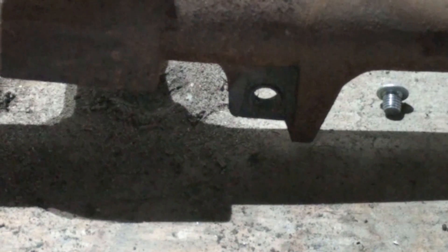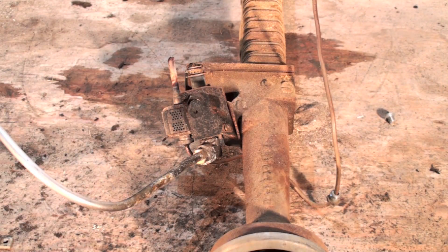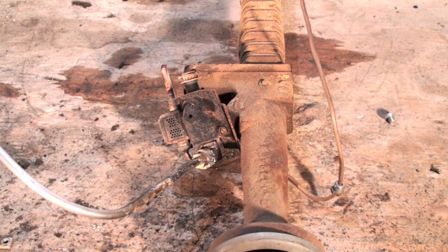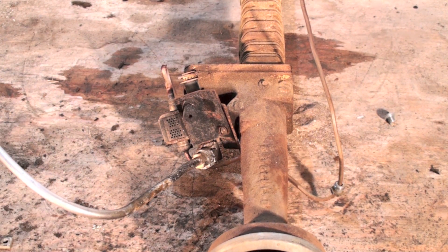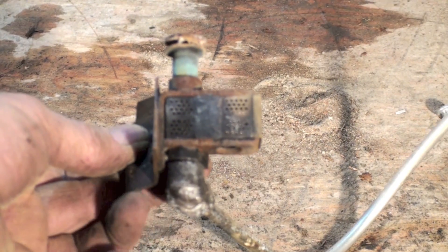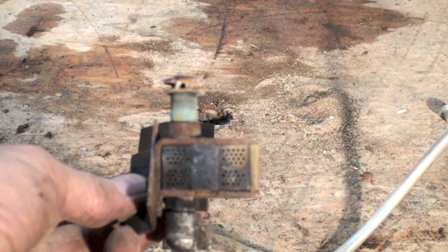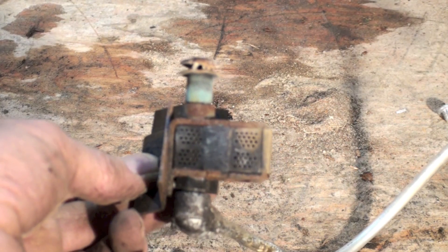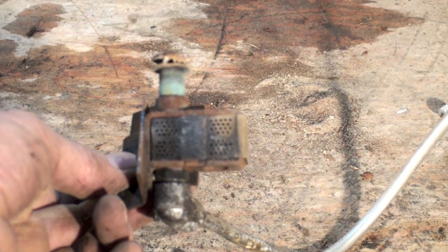Next, I'm going to show you the pilot assembly. Here's the pilot assembly — it sits very tight, just kind of dangling around. I'm going to pull that off and clean it. Here's the pilot assembly when it's off. It looks like it draws its primary air through these little holes here, so I'm going to run a brush over this and knock the debris out.